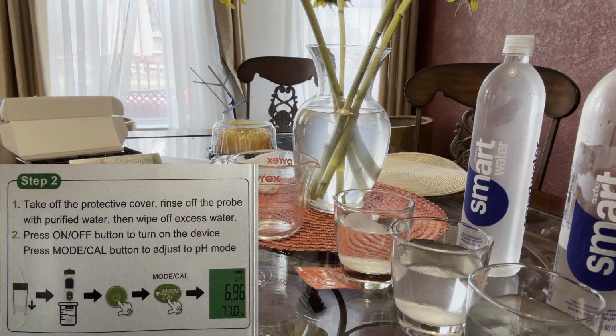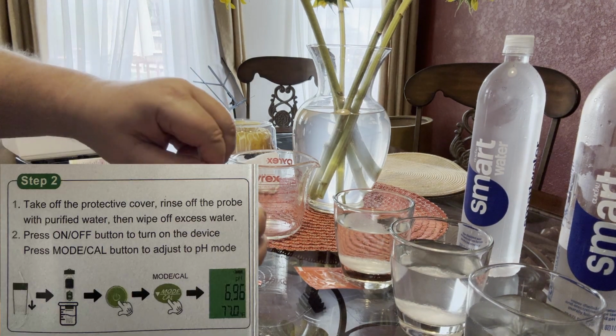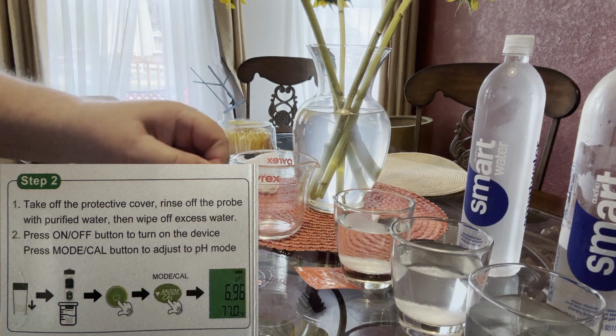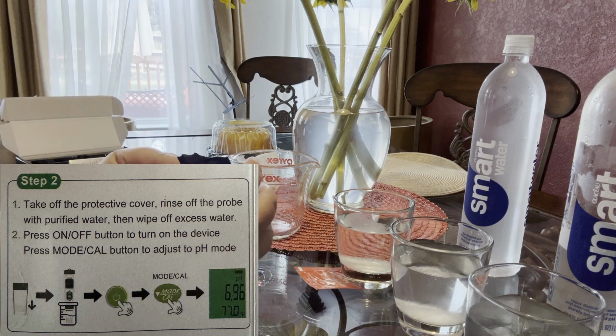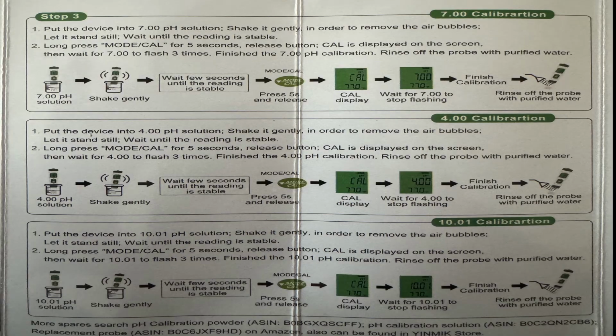Step 2. Take off the protective cover. Rinse and then dry the probe before use. Press the on-off button to turn on the device and press the Mode Cal button to switch to the pH mode. Step 3. Put the device in the 7.00 pH solution. Shake to remove any bubbles. Let stand until the reading is stable, then long press the Mode Cal button when the device is in the solution. Long press means to hold the button down for 5 seconds and then release. Wait for the 7.00 to stop flashing and you're done.